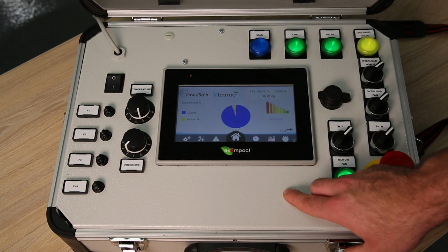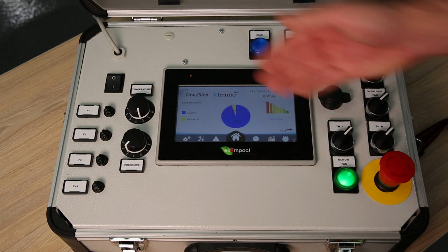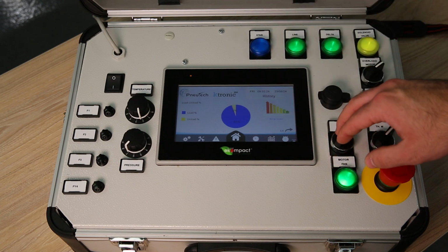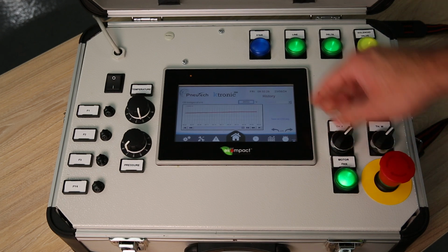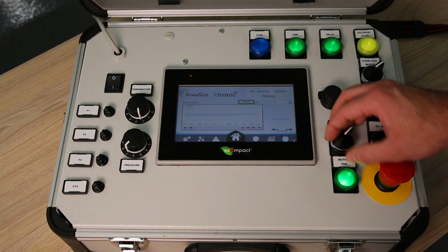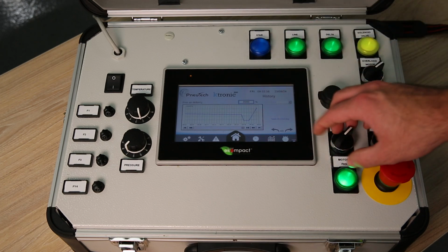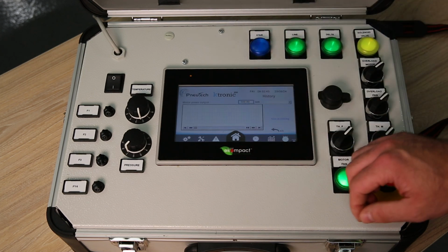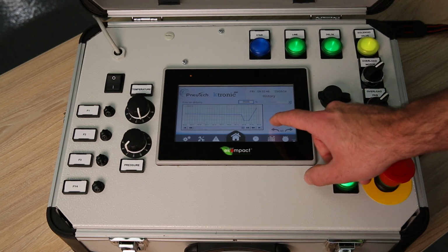Going to the graph setting here, there are a few things that we are monitoring. First, we can see a pie chart of our load and unload hours. This is great for making sure that our duty cycle is within specifications. Going to the second page, we see a graph of our oil temperature over time. We also see our air pressure, our free air delivery, which is just the flow of air from the compressor, the motor speed if it was a variable speed drive, and the motor power output if it was a variable speed drive. All very good things to monitor for the health of the compressor.